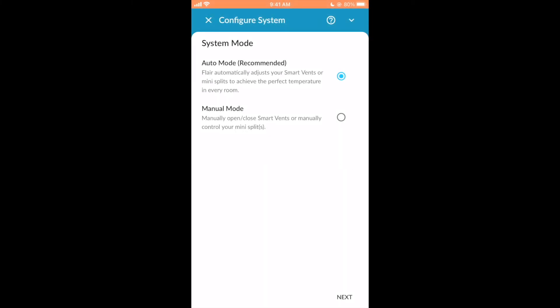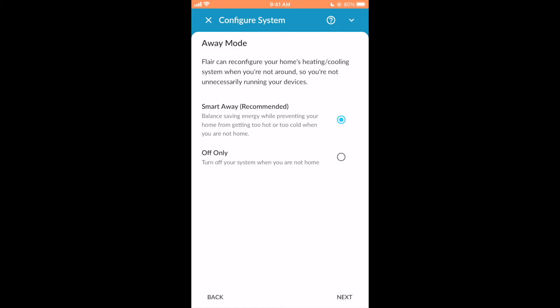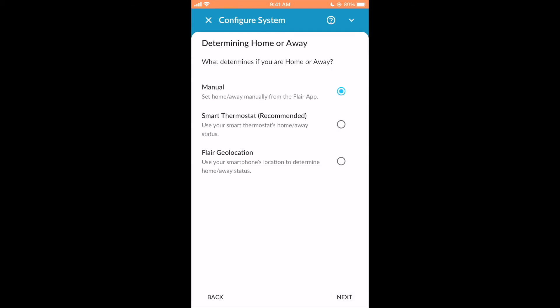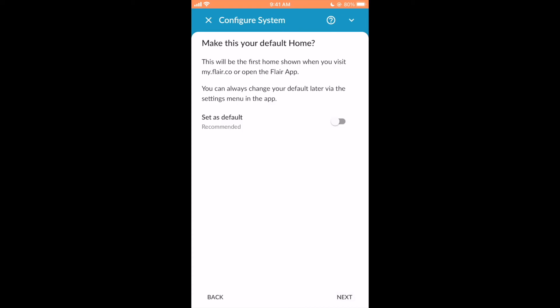Leave system mode to Auto — manual mode can be used for testing mini splits after setup. Set the setpoint control to Flair; this allows Flair to communicate with the smart thermostat. Away mode determines how Flair behaves when no one is home. Choose Smart Away to prevent rooms from getting too cold or too hot, and Flair will keep the home at an energy-saving temperature. Off Only means that Flair will not run heating or cooling and will turn off mini splits. Select Manual to set Home or Away status using the Flair app. Select Geolocation to have the Flair app use the phone's location to determine Home or Away status. Select Thermostat to have Flair read the Home and Away status from the smart thermostat. If you're unsure, select Manual — this setting can be changed later. Away min-max are the temperature bounds used by Smart Away; set these to energy-saving temperatures. Finally, set this Home as the default.